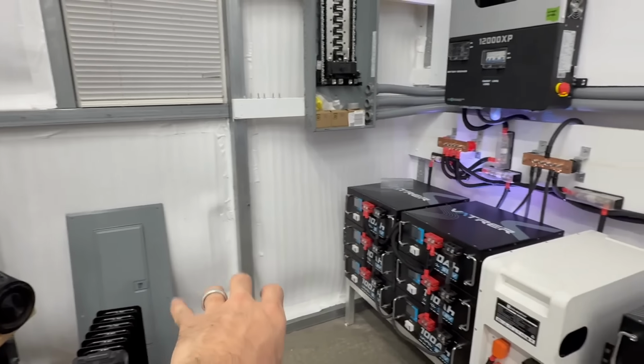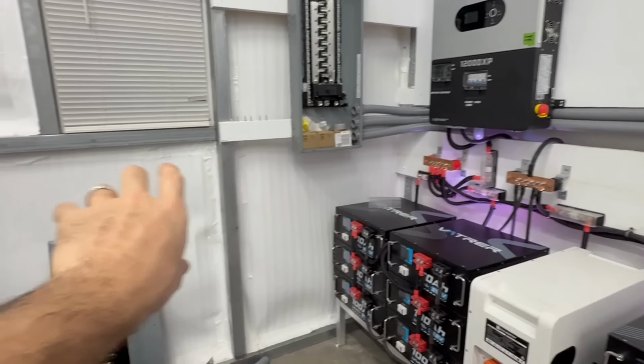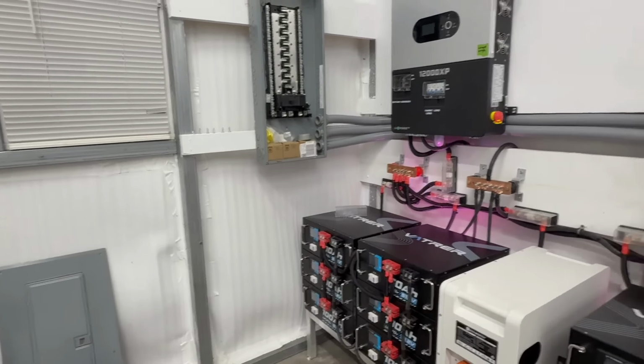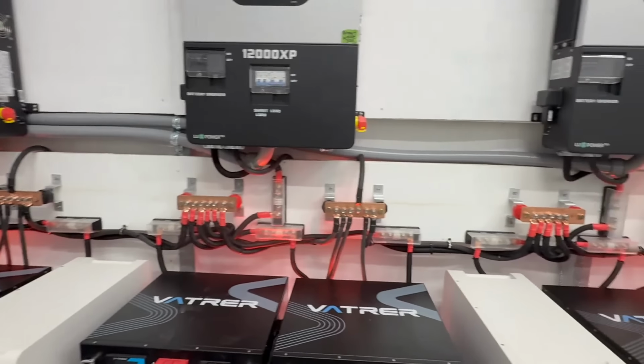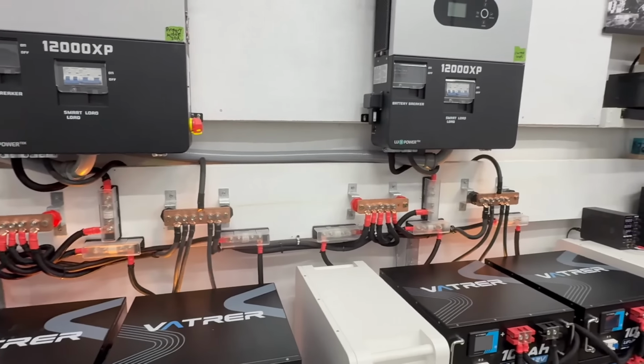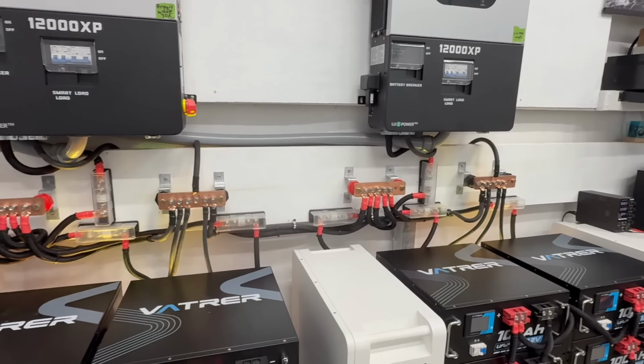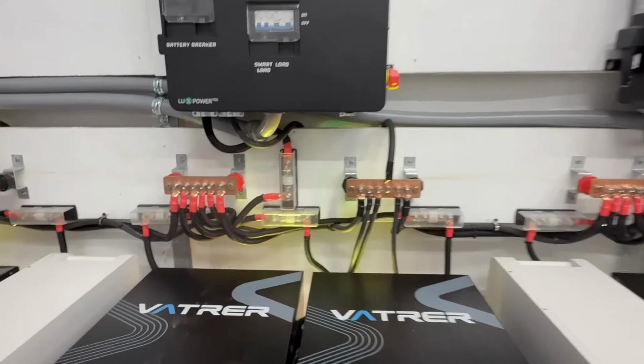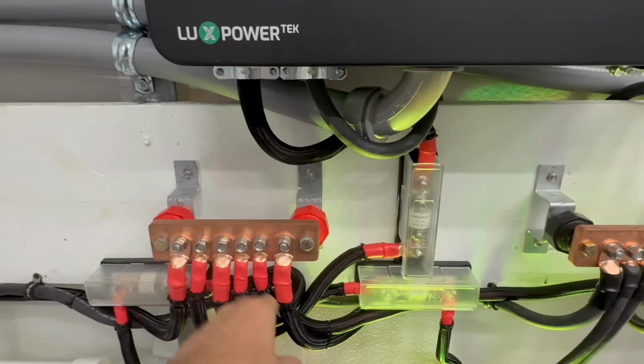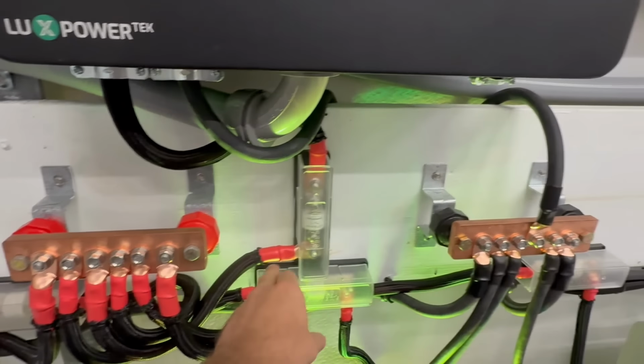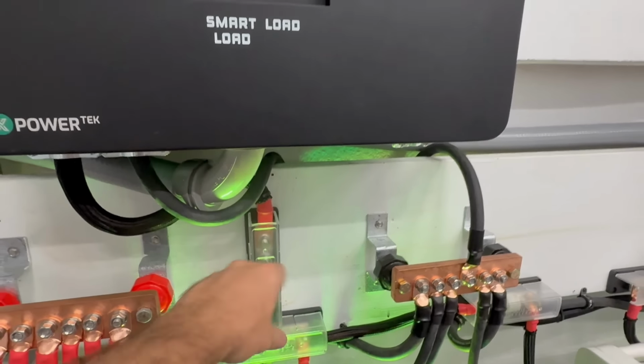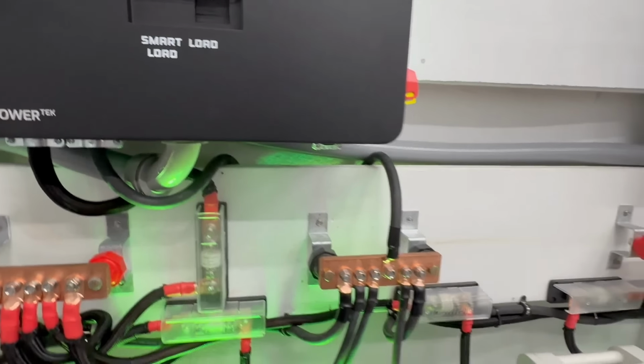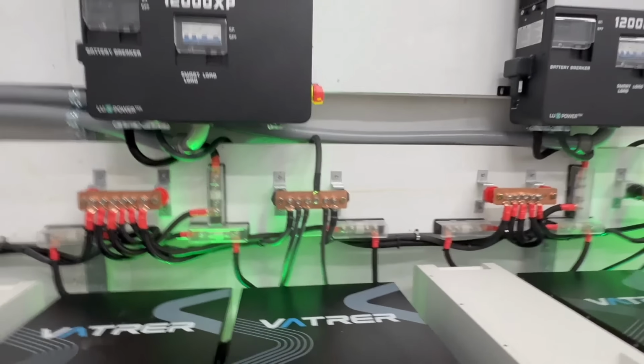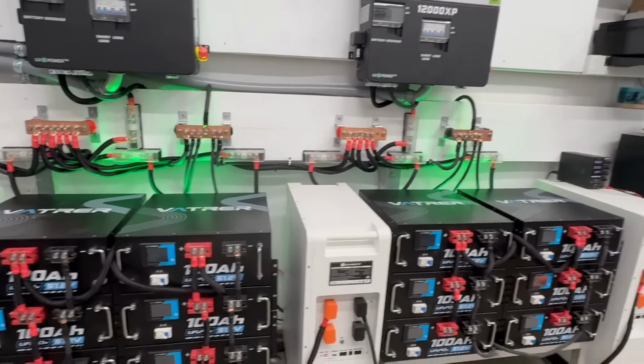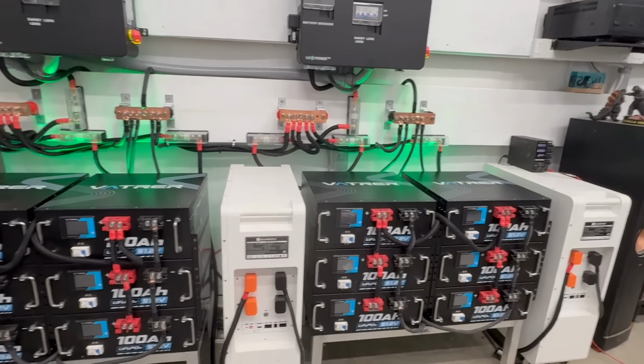So if I wanted to add more batteries over here, all I'd have to do is add a few more bus bars, and I can keep extending the system out without any balancing issues. Once again, I've got my 4-aught cable, it goes up into this T-class fuse, and then into the inverter. So here's kind of what it looks like.